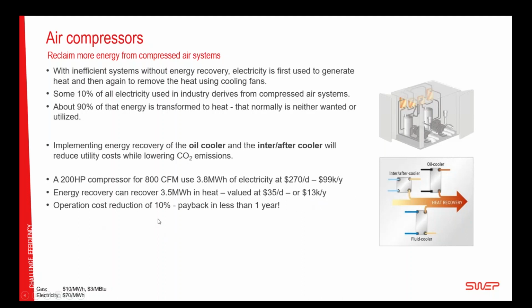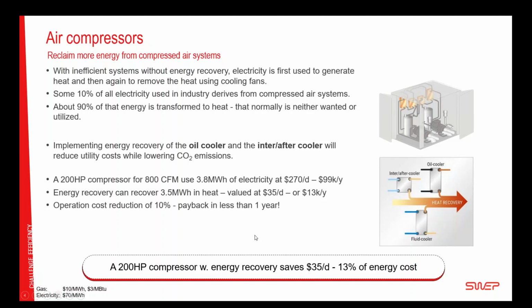It's about 10% of the operating energy cost. And as we saw before, in Europe, or wherever the cost of heating gas is higher, this is going to be of more relative value. But what we have seen is that installing heat recovery for an air compressor rack has one of the shortest paybacks, typically less than 1 year, because the compressor produces so much heat compared to the pressurized air. Yep, moving on.